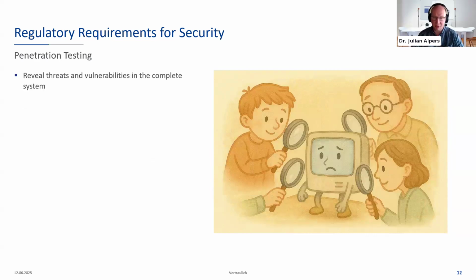The last one is the so-called penetration test. The penetration test reveals threats and vulnerabilities in the complete system. So it is comparable to, for example, a system test or the summative usability evaluation. It's on the validation level of your system. In the penetration test, you want to find as few vulnerabilities as possible, and you want to prevent any critical vulnerability from being found, because everything you find in the penetration test costs a lot of money.